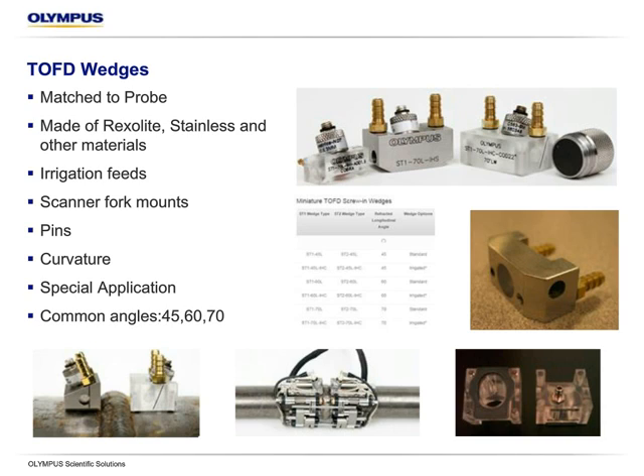Then we have special application type things. The bottom right is actually a wedge made for HDPE pipe. This has a water interface and a seal. The reason we do this is because the natural velocity of HDPE and other plastics is too close to Rexolite, which can cause issues in getting proper beam propagation. By using water, we're able to do that very easily and conveniently.